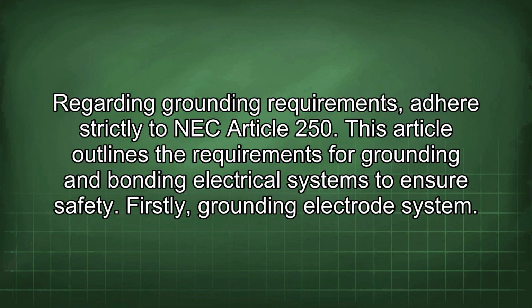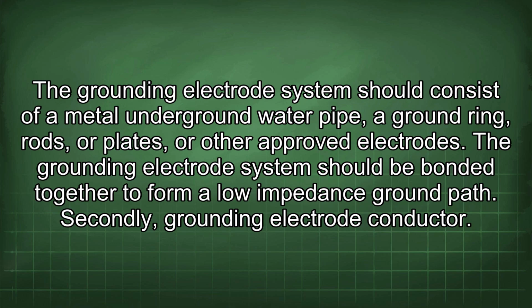Regarding grounding requirements, adhere strictly to NEC Article 250. This article outlines the requirements for grounding and bonding electrical systems to ensure safety. Firstly, grounding electrode system. The grounding electrode system should consist of a metal underground water pipe, a ground ring, rods, or plates, or other approved electrodes. The grounding electrode system should be bonded together to form a low impedance ground path.